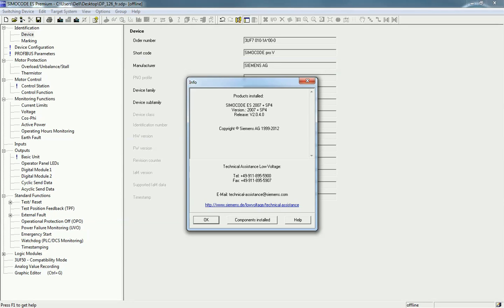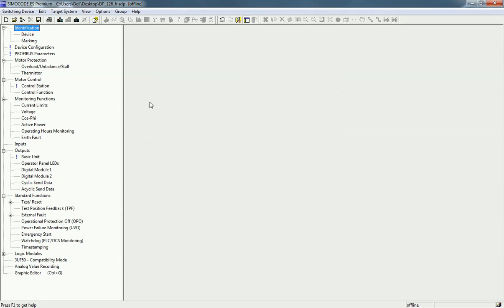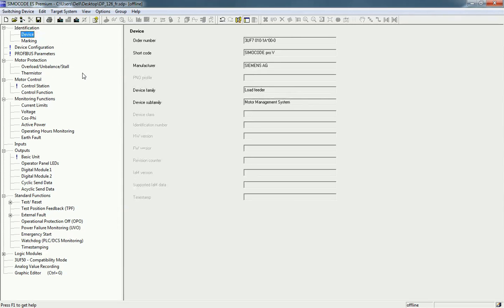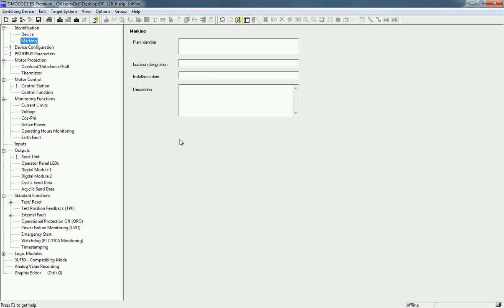I have SIMOCODE ES 2007 SP4 version installed on my PC and I have a license for the software. Starting from the Identification section, there are two options: Device and Marking. From Device, you get details like order number, short code, manufacturer, and device family. Right now we have SIMOCODE Pro V with a short code and order number. In Marking, you can define installation date, location, designation, and a description about the project.